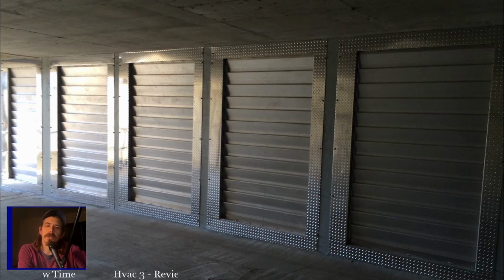But it is a good way to determine, okay, is my signal going to the thermostat and back from the thermostat to the unit? And it's important to recognize, that wire might be messed up coming back from the thermostat. And if you need to determine that, then you need to jump those wires at that location to figure it out. So, along with understanding what those different terminals are for, what R is for, Y is for, W is for, G is for, so on and so forth.